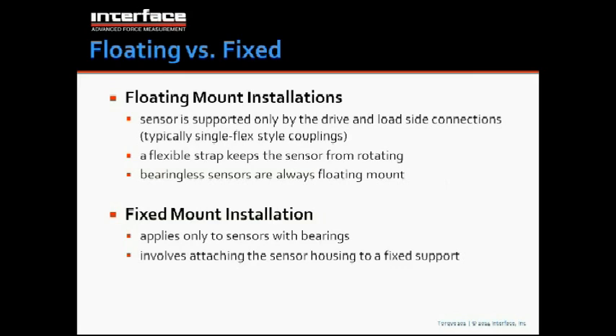A floating mount installation is where the sensor is supported only by the drive and load side connections. And so it basically floats in the middle between two components. In a rotary sensor, the housing is going to want to rotate along with the sensing element, and so a flexible strap is used to keep it from rotating. Bearingless sensors are always floating mounted because they don't have any bearings, so they cannot be supported except by their end connections.